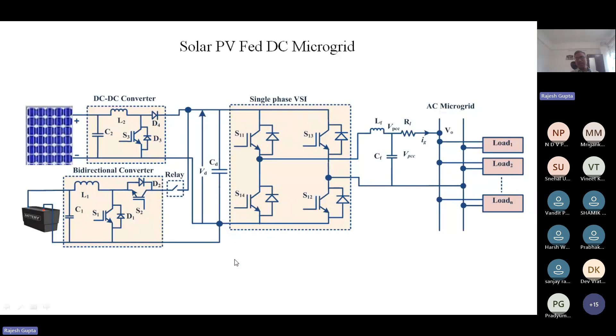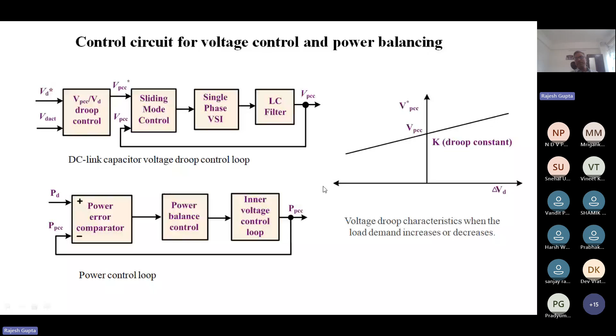Now, one of the important things as far as control is concerned is what we call a droop control characteristic, which is required in a DC microgrid, because it is kind of a floating system. So the voltage at the PCC bus needs to be controlled in order to maintain the power balance. So this is a DC link capacitor voltage control loop, and this is a power balance loop. We have to look at both in order to make a control.